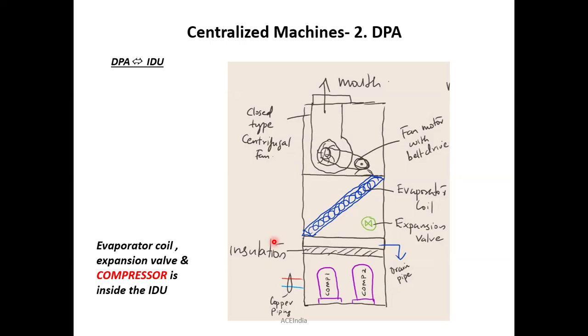Hello? Tell me guys, do I need any external suction line connection? No, isn't it? Why? Because it's already built in, right inside the machine. We don't need any external copper piping for that suction line. But we need another connection which connects the compressor to the condenser, isn't it? So what should that line possibly be called? Any idea? What is the specification of the refrigerant leaving a compressor? You said it has to be a superheated vapor, isn't it?